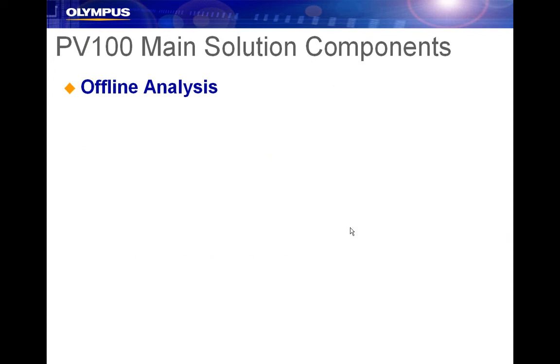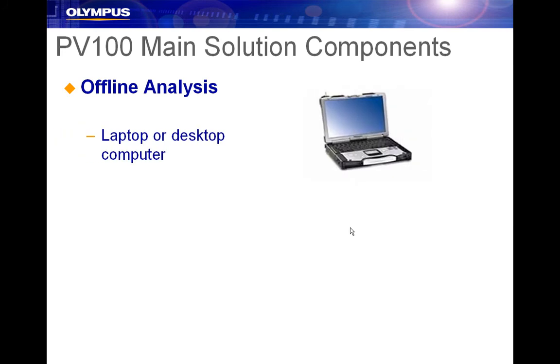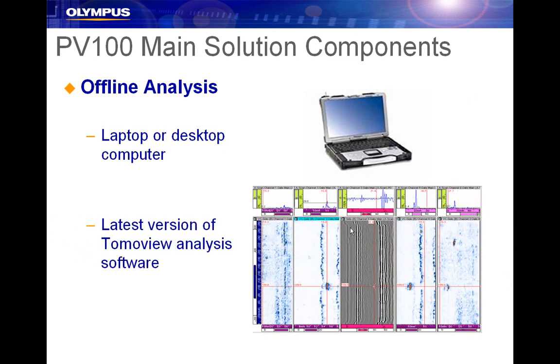TomoView analysis software is used to analyze all scans after acquisition. A configured industrial-style laptop can be acquired with all the necessary software to analyze and report findings. Shown above is a typical data display with TOFD data in the middle, along with shear wave channels. All channels are linked by position, so defects can be verified, analyzed, sized, and reported from multiple channels. The shear wave channels are typically set to an amplitude response palette, so defects reaching reject level can easily be discerned by color. Measurements can be acquired by cursors, gated readings, and contour boxes. The results can be reported directly out of TomoView into a Windows-friendly format for easy distribution.